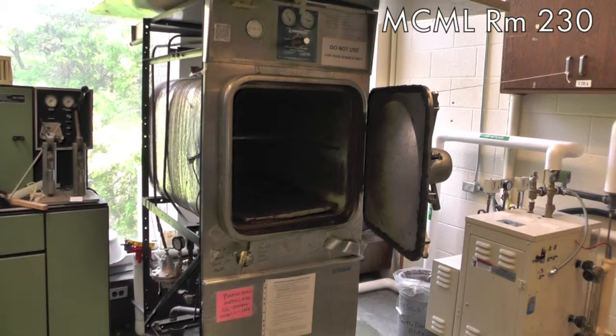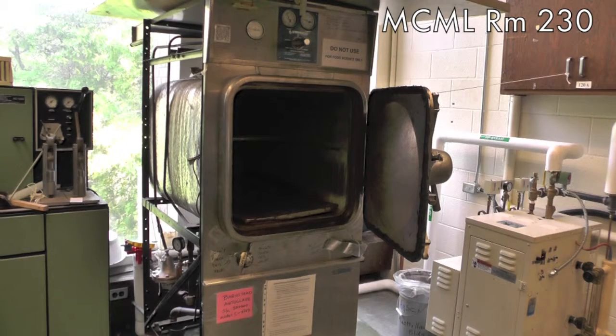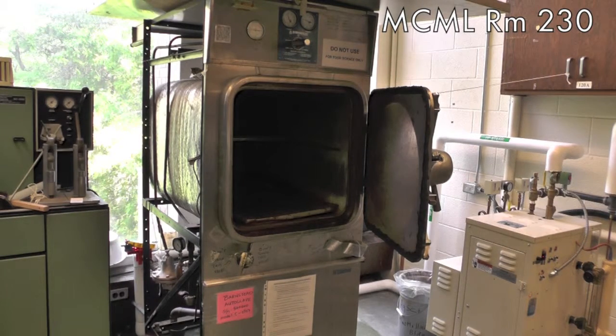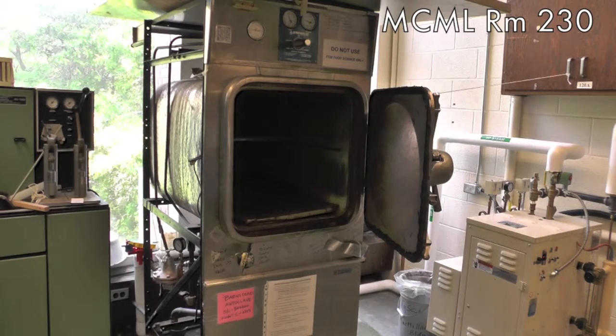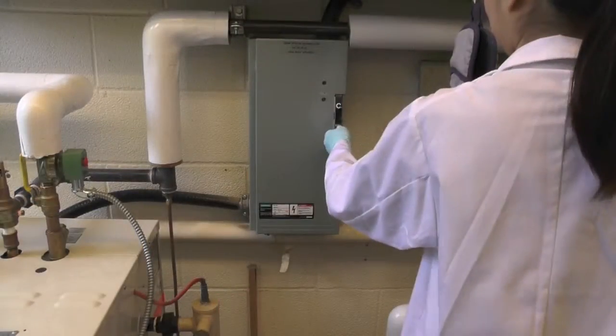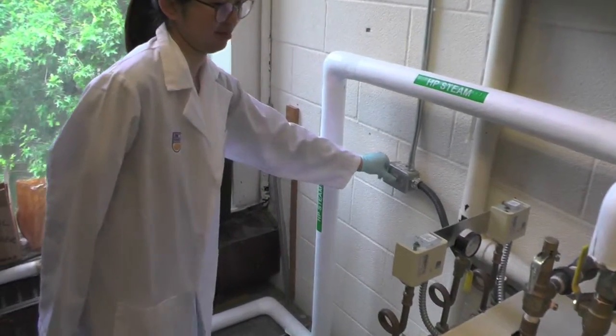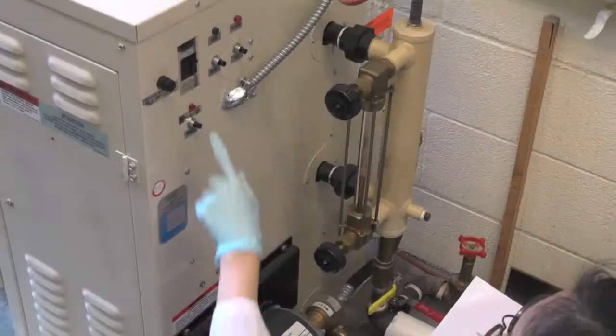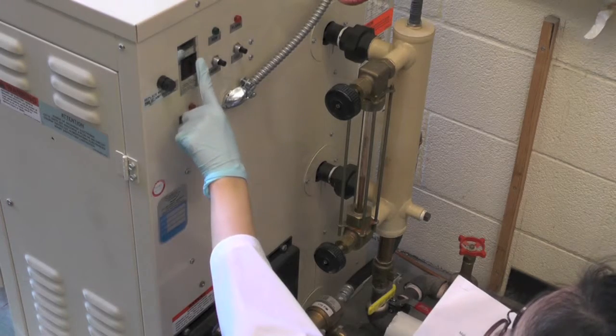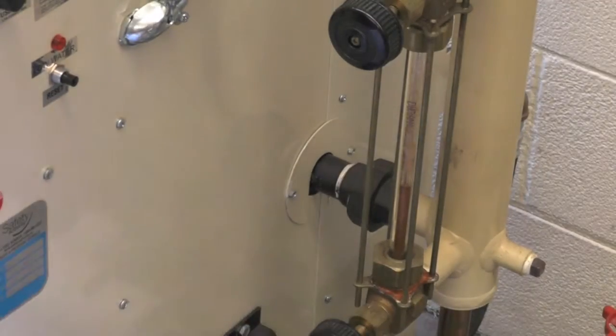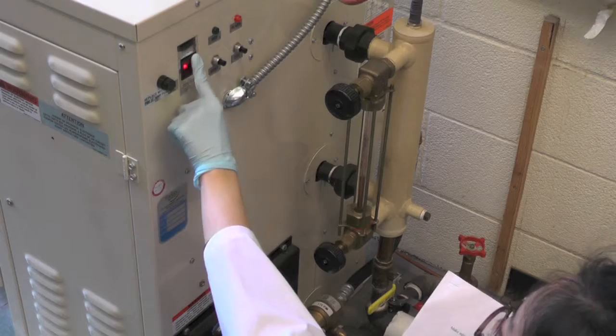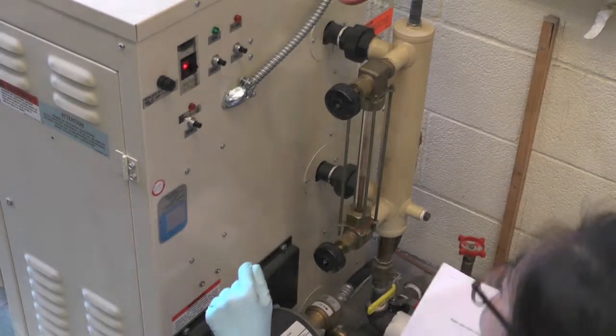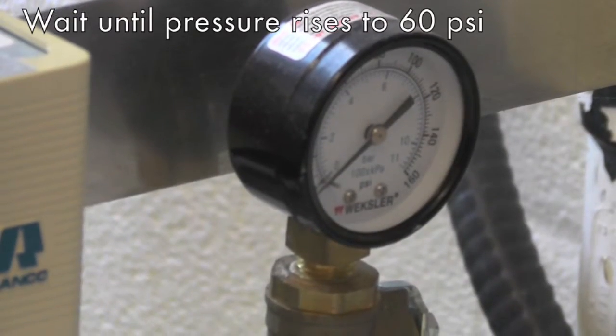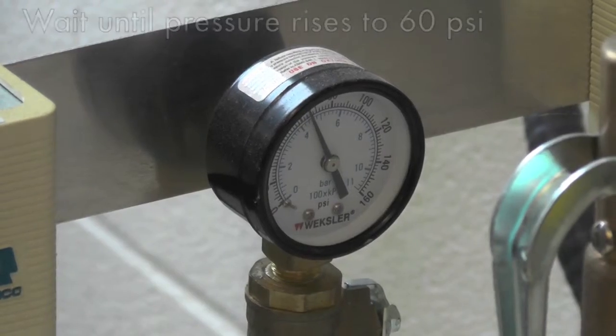This video will demonstrate the standard operating procedure for autoclave. This is the autoclave located in Macmillan room 230. First, turn on the steam generator beside the autoclave by turning on these three components in order. Before switching on this component, make sure there is water in the glass tube because this indicates that the pressurizer is working. Wait until the pressure of the pressurizer rises to around 60 psi.